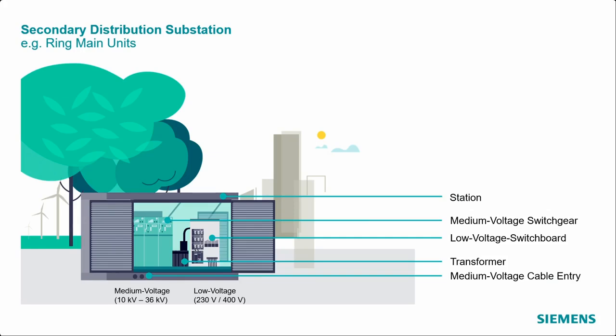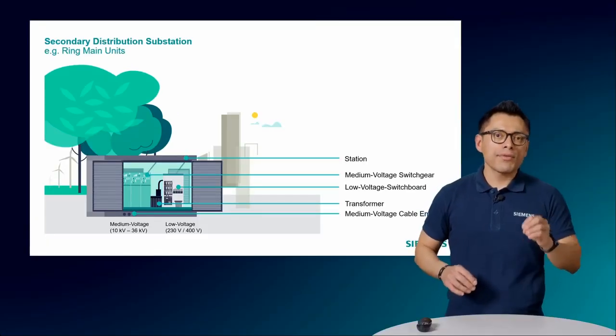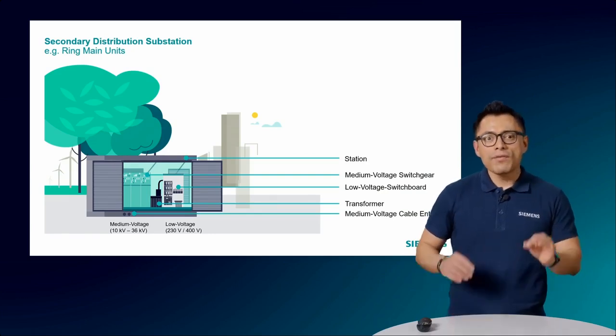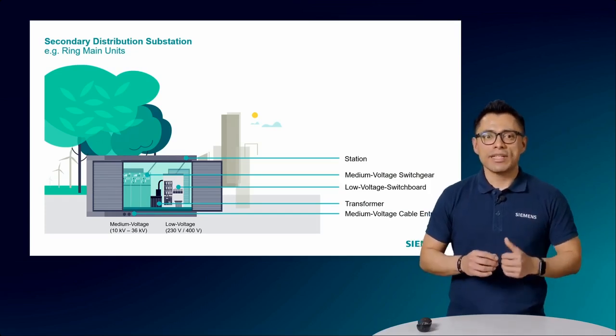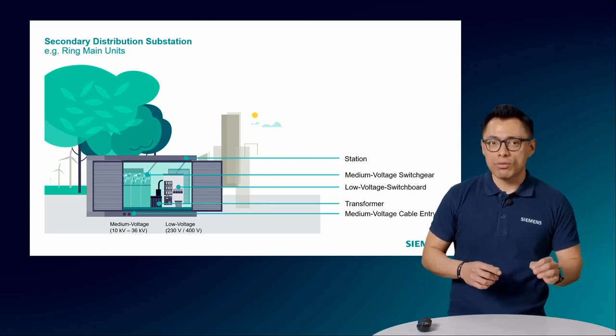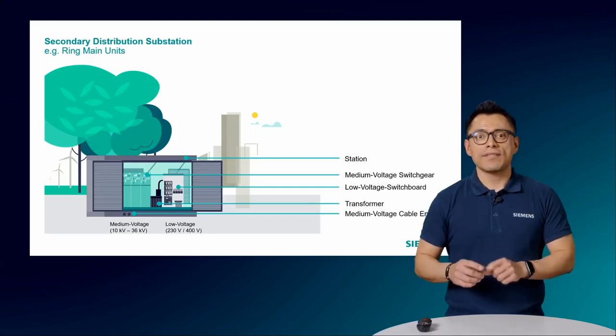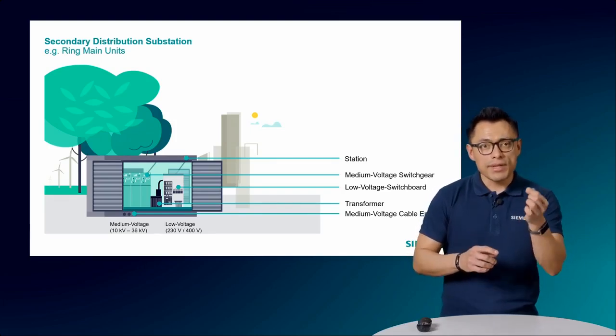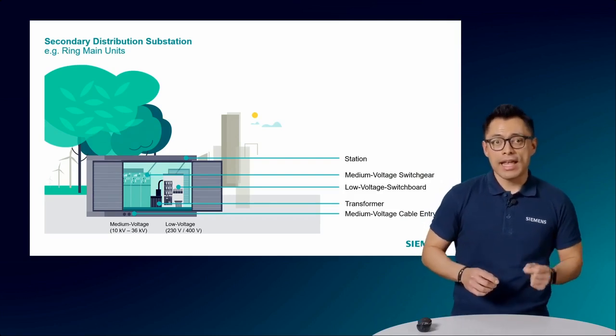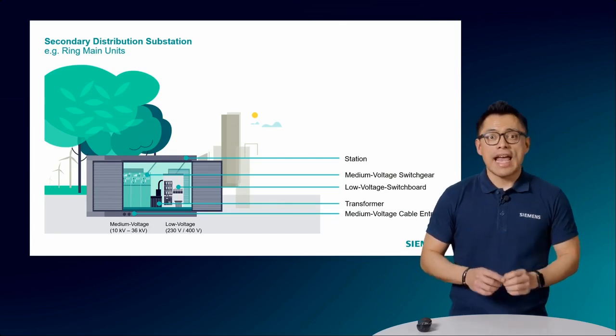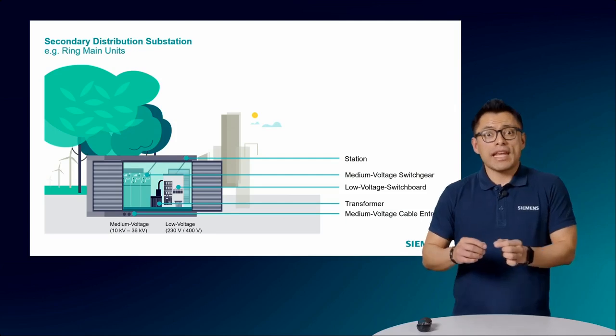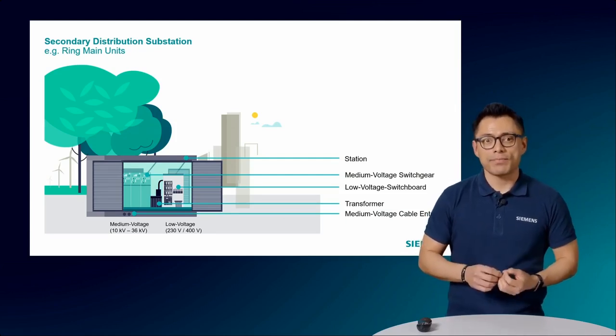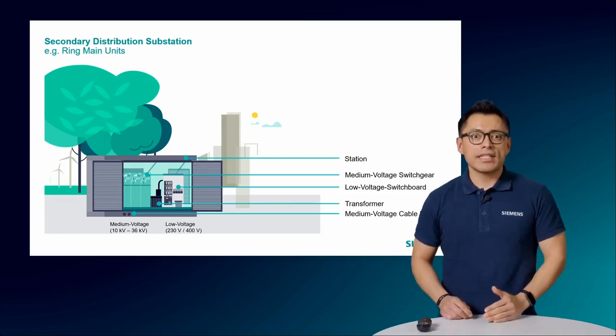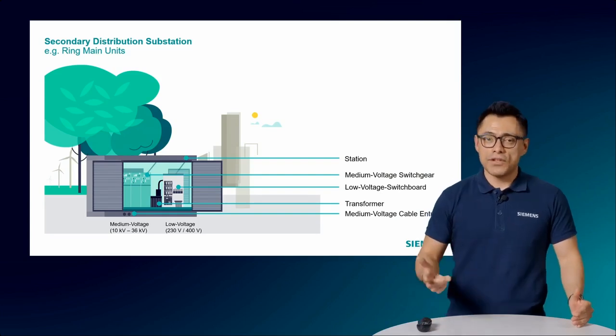Typically, at this point, the cable infrastructure flows underground. However, depending on the design and existing infrastructure, sometimes it can also be via overhead lines. Now let's focus on some of the main functions of secondary distribution substations. One very common function is protection and control, as they include circuit breakers and/or fuses to safeguard the distribution network from faults and overloads. Another function is voltage regulation, as they keep the voltage levels within specified limits to ensure a stable and safe power supply. And the last function is monitoring and communication, as they have systems to monitor the performance and to communicate with the central control systems for efficient management. These tasks ensure that electricity is delivered to the end user safely, reliably, and efficiently.